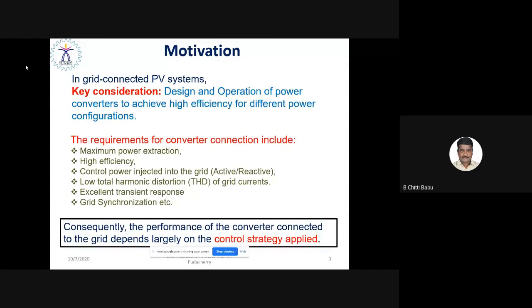And of course, while you're injecting AC power into the utility grid, the grid current must have a lower harmonic distortion. So that is one of the great challenges while you're integrating renewable energy with the utility grid, because basically the power converter provides an asynchronous interface. So of course, there may be the pulse width modulation and the switching strategy. Also, due to non-linear load which is being connected at the point of common coupling, there must be a distortion in the grid current.